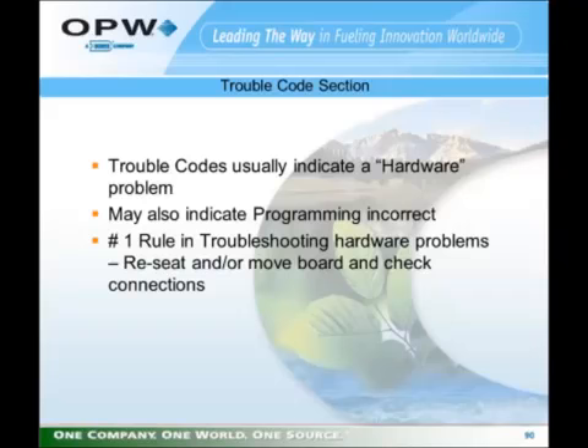The number one rule is to make sure that everything is seated properly, everything is connected properly, and that things haven't been moved around or that someone has not changed something in the program that should not have been changed. An easy method to troubleshoot indicated hardware items like a probe or a sensor would be to swap that device with a working device to see if the trouble follows with that probe or sensor. If you suspect field wiring may be the issue, you could bring those devices inside the building and hook them directly up to the unit and test them that way.